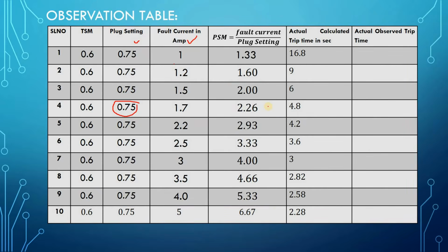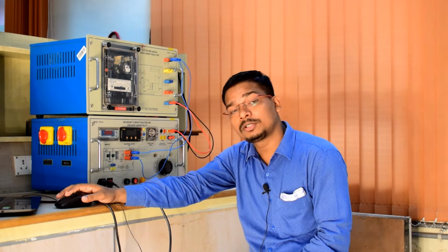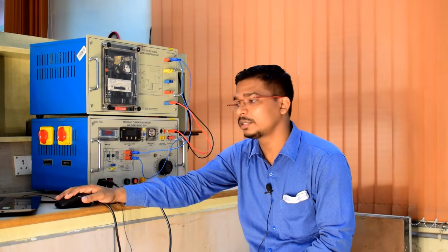Let's see an example. Let's say 1.5 ampere of current. So here the 1.5 ampere current is fixed, and 0.75 is the plug setting. Correspondingly you are getting 2 as the PSM. So if you are getting 2 as the PSM, then, as I showed you earlier, corresponding to that...